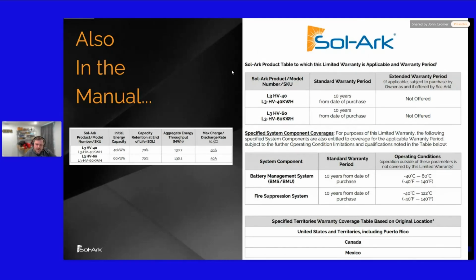One thing I'd say about our warranty compared to others is that it includes the battery management system, and it also includes the fire suppression system. This is something you have to look out for. Say, the fire suppression system of some of our competitors: they'll give you a 10-year ESS warranty, but the fire suppression is only a 1-year warranty. So it's like, well, do you really want to go into each battery module and open up each battery module once a year and replace the fire suppression system?